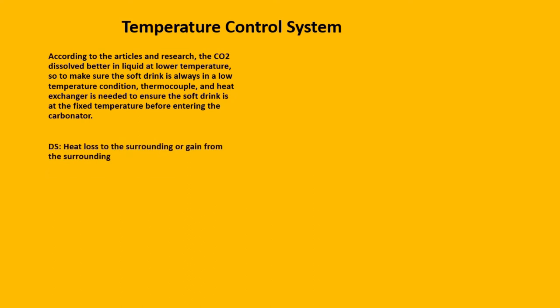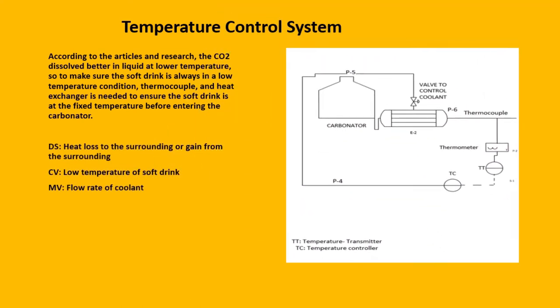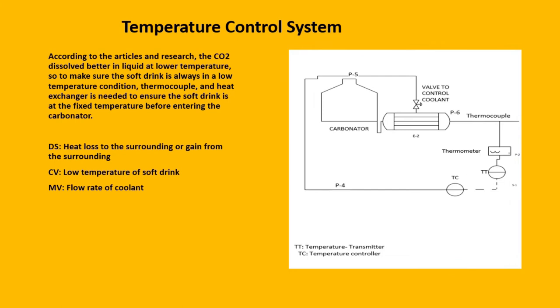According to research, CO2 dissolves better in liquid at low temperature. So, to make sure that the soft drink is always in a low temperature condition, a thermocouple and a heat exchanger are needed to ensure that the soft drink is always at a fixed temperature before entering the carbonator. The control variable during this time will be the temperature of the soft drink, and the manipulated variable will be the flow rate of coolant. There will also be a disturbance variable, which is the heat loss or gain to and from the surrounding. When the temperature of the soft drink increases, the temperature transmitter will send a signal to the comparator in the form of electrical current. The comparator will compare and calculate the error between the set point and the signal received. The controller will give a correct output to the valve for the coolant to increase the flow rate of the coolant and cool down the soft drink to allow CO2 to dissolve better.